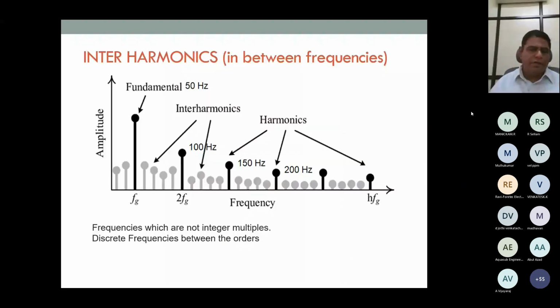So what about interharmonics? This is just for informational purposes. This is the fundamental frequency, 50 hertz. This is the first, second order, 100 hertz. This is the third order. In between, there will be frequencies like 60 hertz, 70, 80, 90. If these are present in a system, these are called interharmonics. These are not integer multiples; these are discrete frequencies. Interharmonics normally come in fabrication shops where welding is involved using inverter based welding machines. In foundries, other than gray iron foundries, we have not seen such interharmonics much in volume.